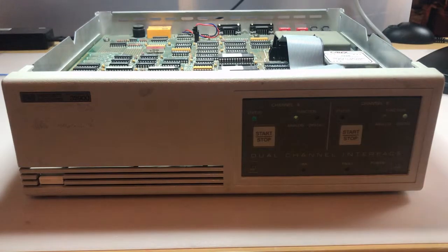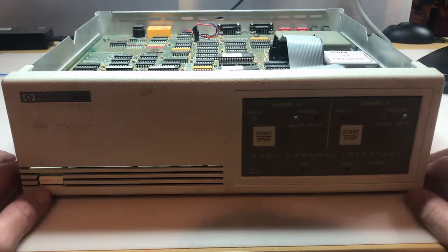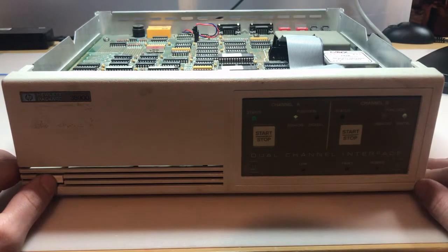Okay, so as I said earlier, the service manual is very lacking. Not only doesn't it have schematics, but it also doesn't provide any information for the error codes. What it does say though is that at startup you do have to have your communication cables hooked up to your PC, and if you don't, you're going to have that fault light remaining. So I think that's what our issue is. It doesn't say anything about specific fault codes, so I can't know for sure, but I believe that's the issue. I have no reason to believe that this unit wasn't working before, and it simply just stopped working because that inductor trace eventually wore and broke free, and so power failed to the unit.